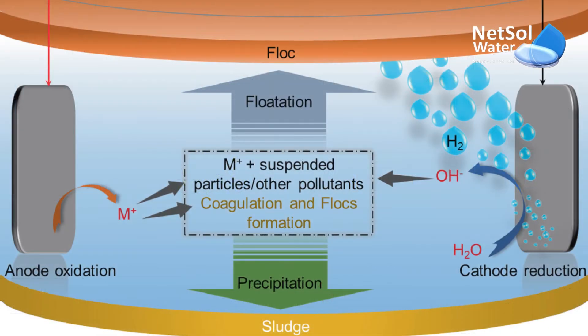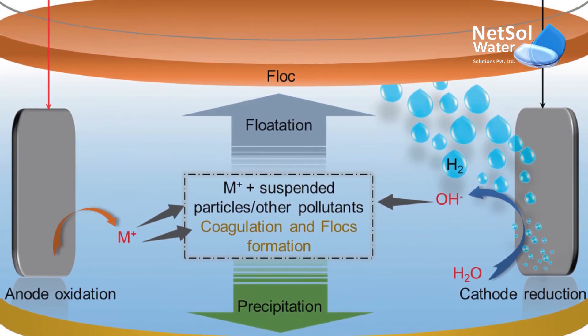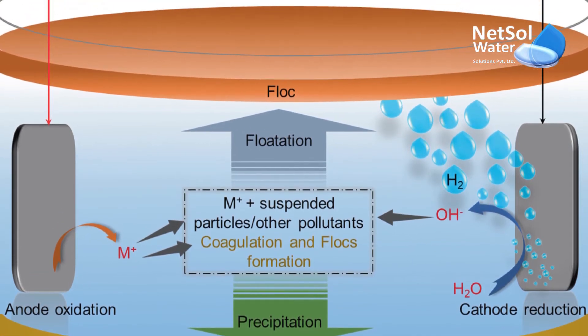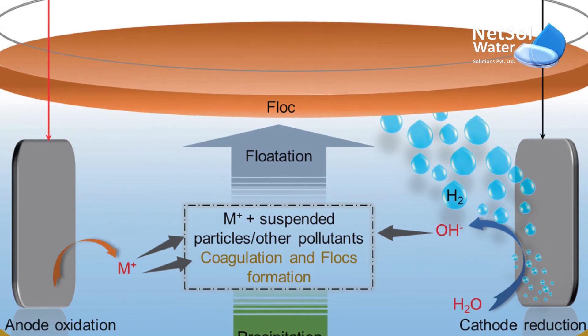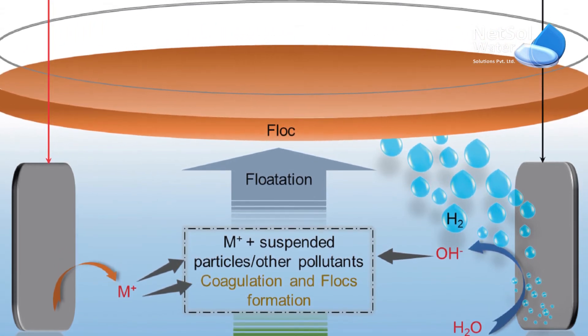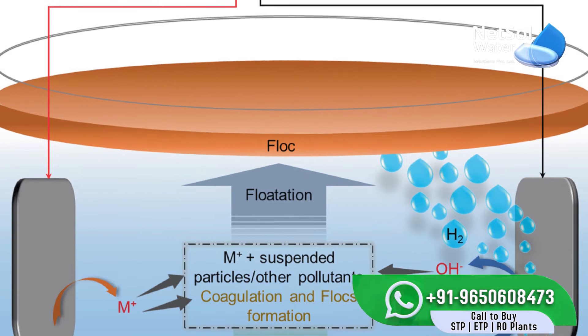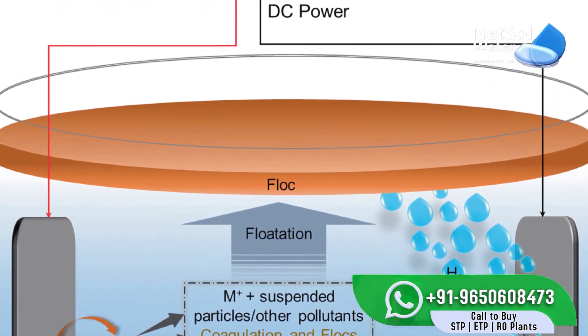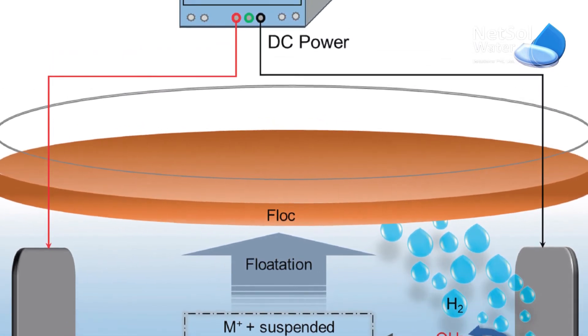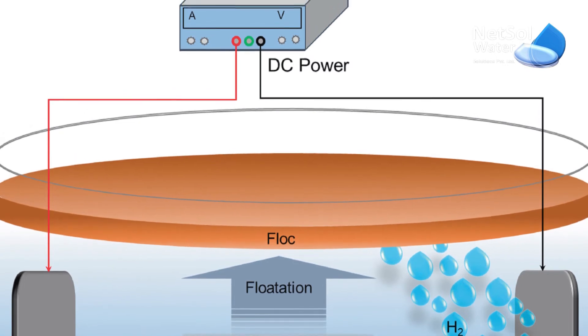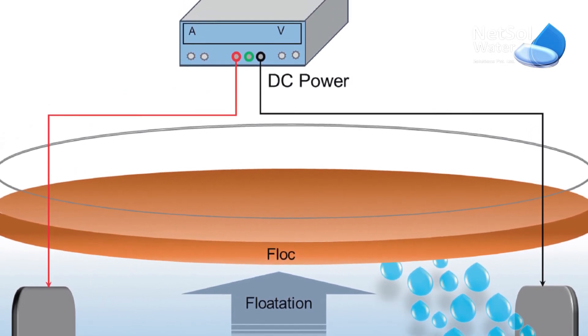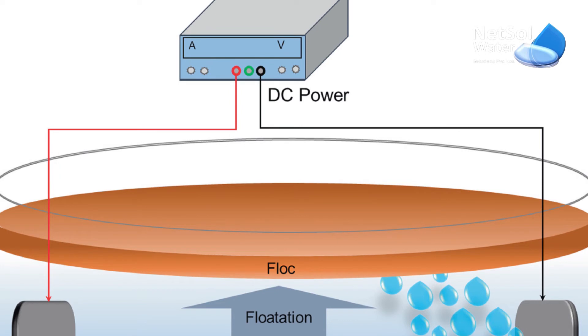The second stage is destabilization of contaminants, emulsions, and particulates. In this stage, the ions produced by the sacrificial electrode's oxidation interact to compress the diffuse double layers surrounding charged contaminating species. Ions created by the dissolution of the sacrificial electrode neutralize the ionic species in wastewater, reducing electrostatic inter-particle repulsion. When this repulsion is reduced, Van der Waals attraction takes over and causes coagulation.